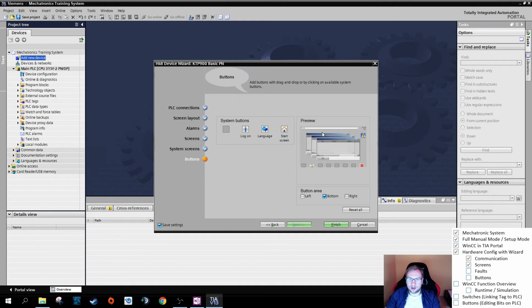Exit closes the runtime, meaning the project that we are programming right now is going to be closed, and we are back at the initial setup of the HMI, which is usually a Windows running, where you can access the system information, the system settings, everything that you can usually access in Windows. So I'm going to leave that on. Maybe you need to change the IP address, then you have to close the runtime and change the IP address in the system settings, as in all Windows.